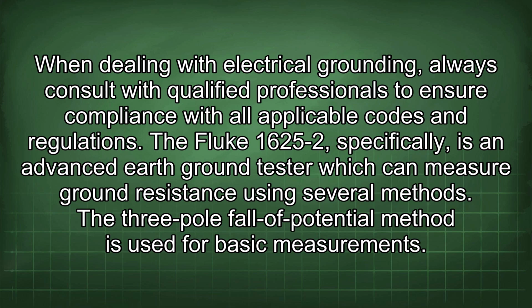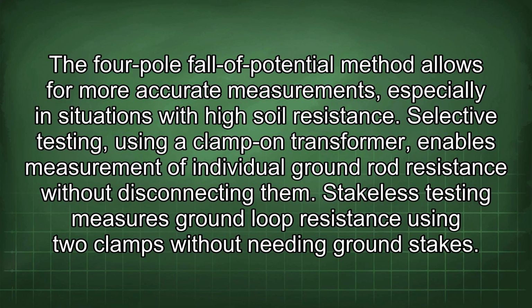The 3-pole fall of potential method is used for basic measurements. The 4-pole fall of potential method allows for more accurate measurements, especially in situations with high soil resistance. Selective testing, using a clamp-on transformer, enables measurement of individual ground rod resistance without disconnecting them. Stakeless testing measures ground loop resistance using 2 clamps without needing ground stakes.